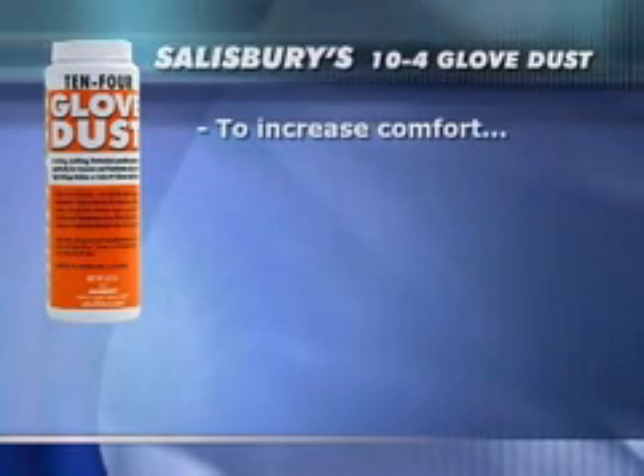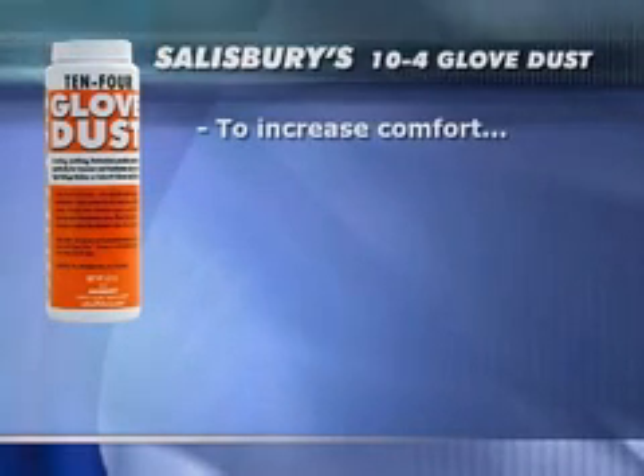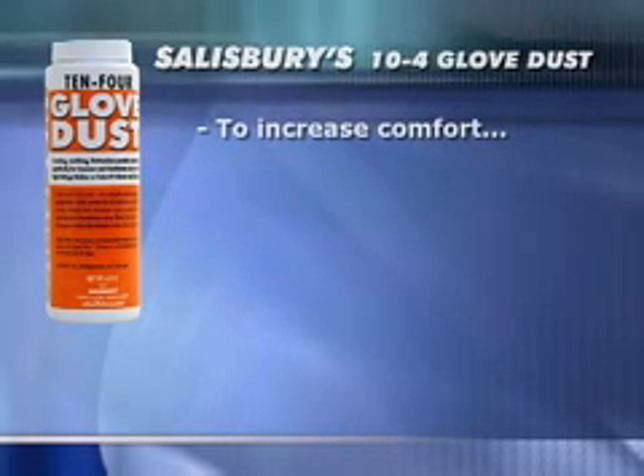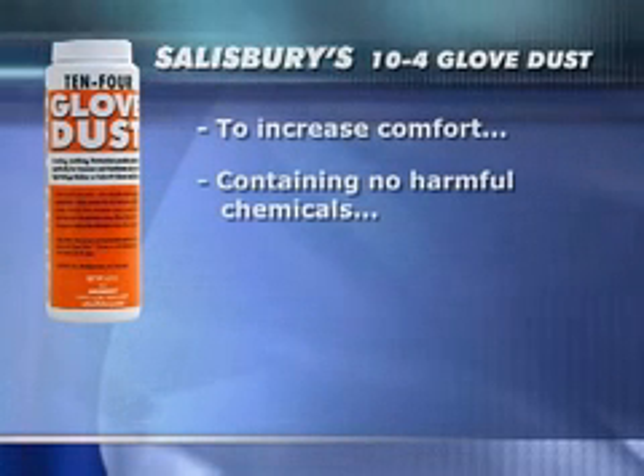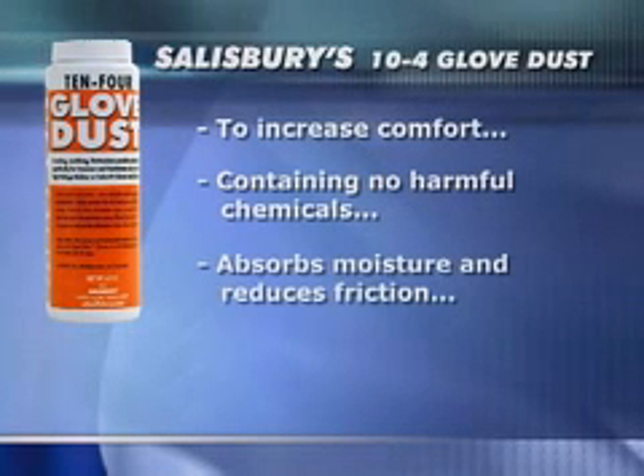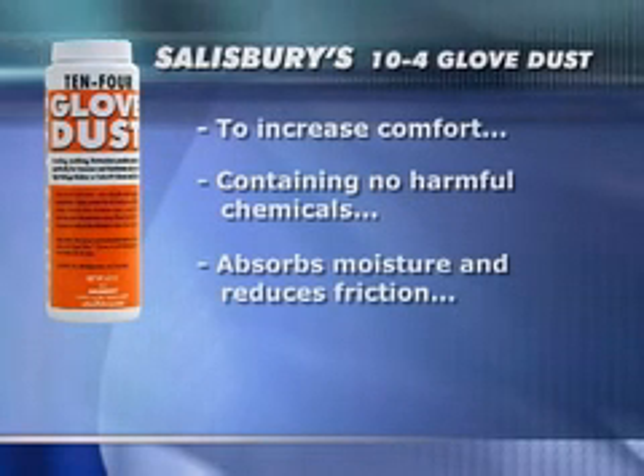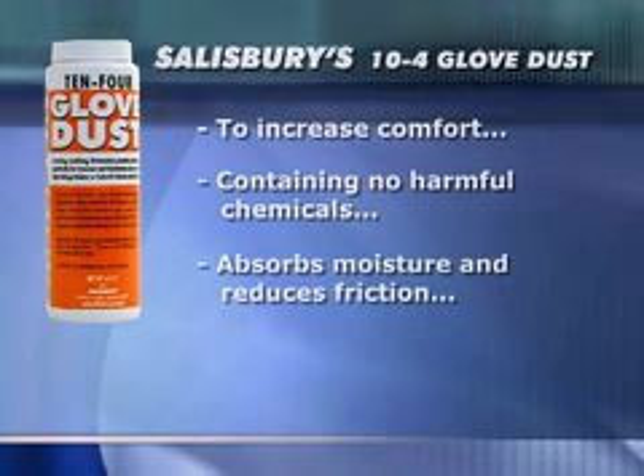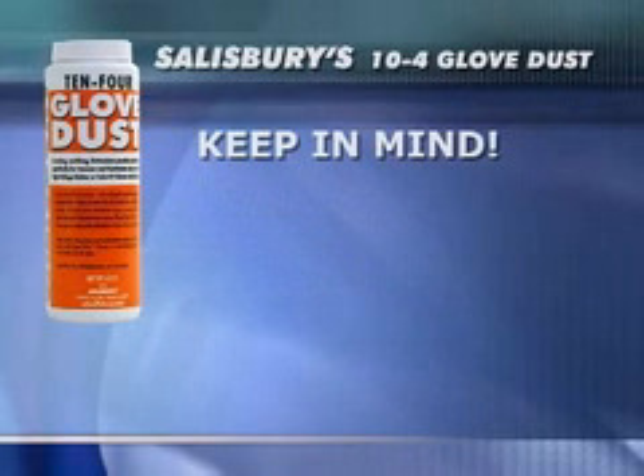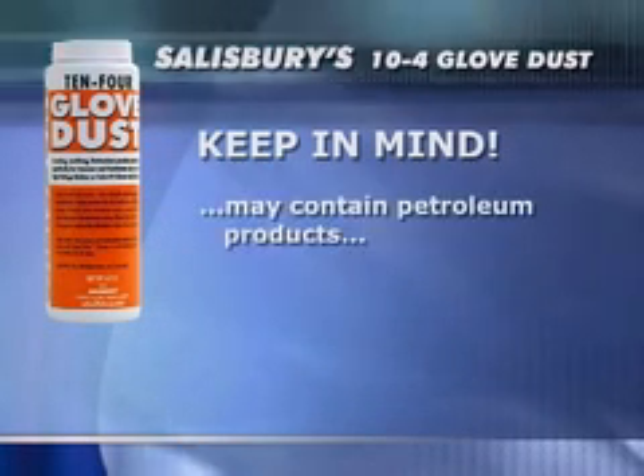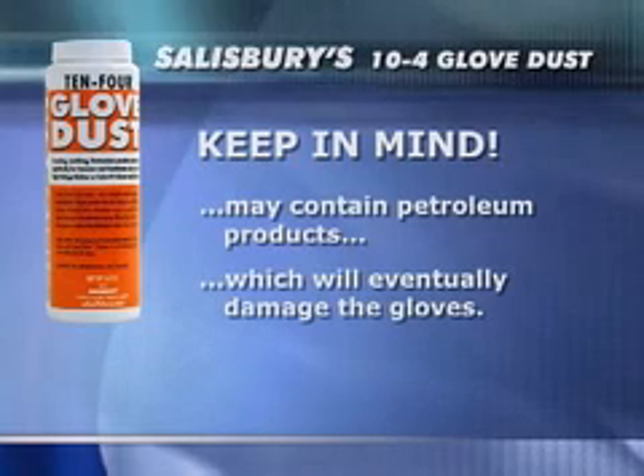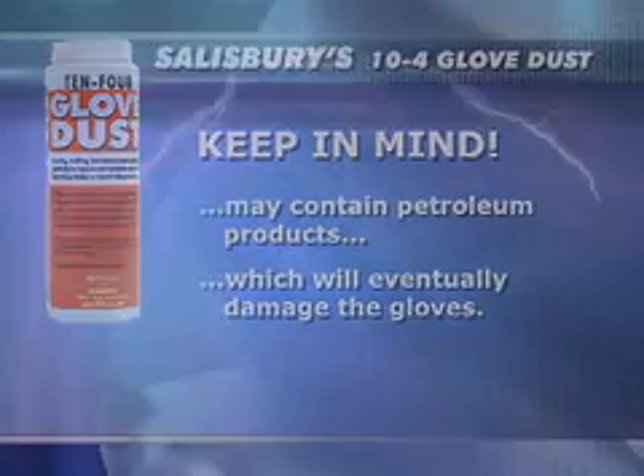To increase comfort when wearing rubber gloves, use Salisbury's 10-4 Glove Dust. Containing no harmful chemicals, 10-4 Glove Dust absorbs moisture and reduces friction for comfort and increased safety. Keep in mind that baby powders or medicated talcs may contain petroleum products, which will eventually damage the gloves.